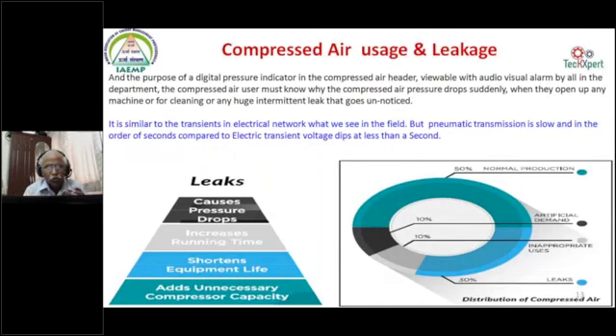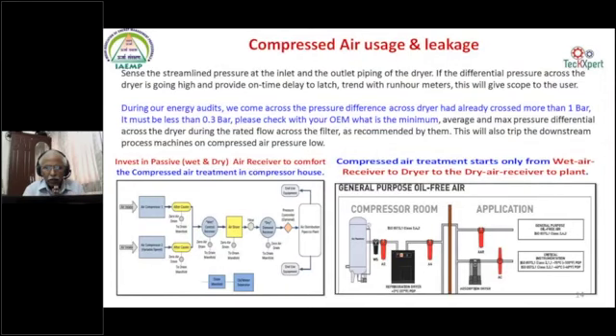Pneumatic lag is more, so that needs buffers at each and every place. In some of the machines, you will find air bottles to have an adequate buffer space, so that whatever the equipment draws will be maintained by the air bottle fitted at the bottom of the equipment. You see the right bottom diagram, it shows the wet receiver and the dry receiver, and the automatic drain valves have to function in the receivers, in the post coolers, and in both the receivers and the refrigeration dryer.